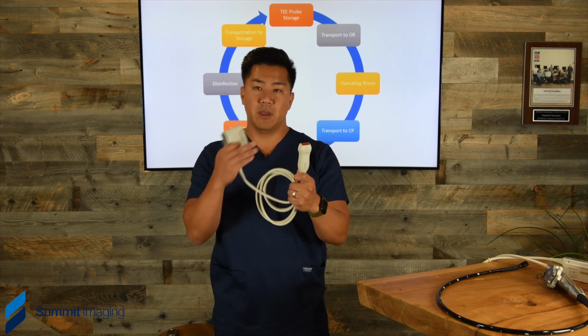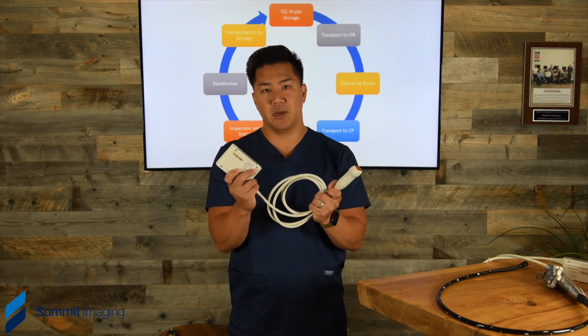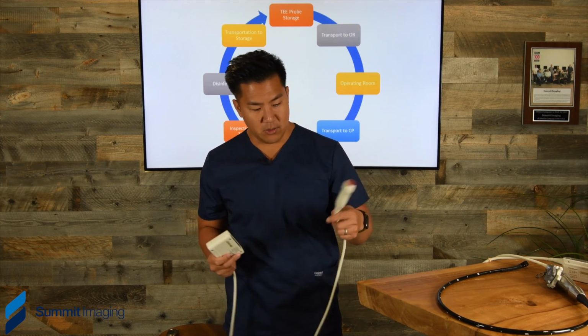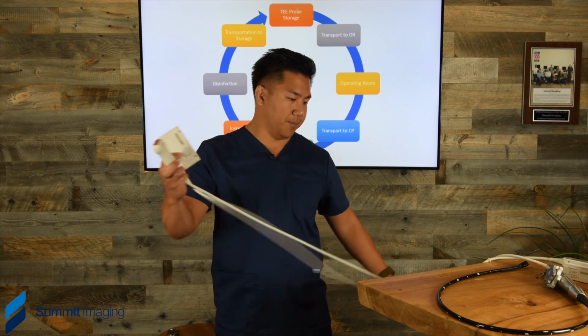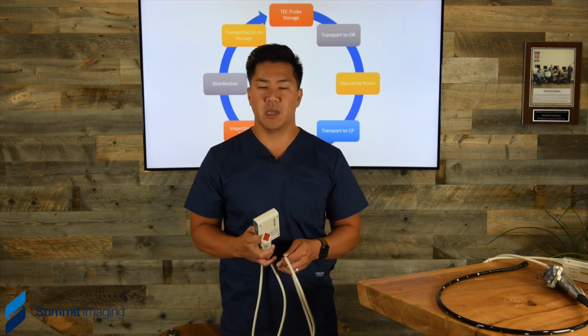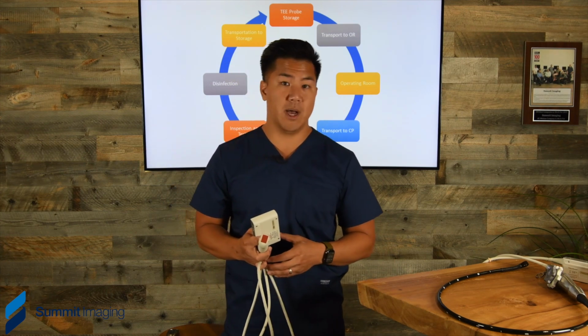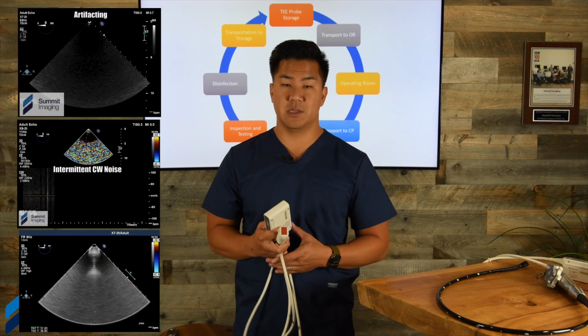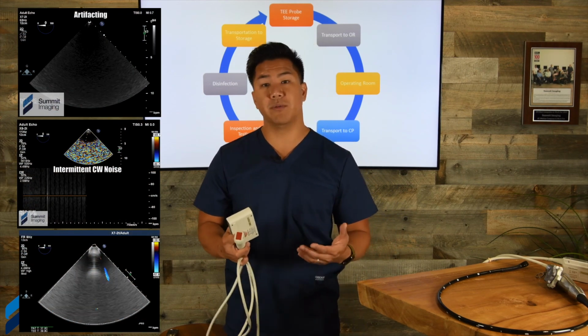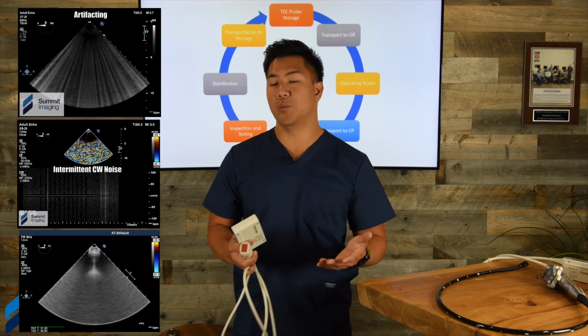Keep the probe head away from the connector, and don't accidentally bang it on these really hard surfaces. That will rattle the electronics well, and you'll start seeing failures in image quality first, and then ultimately the probe just won't run anymore.